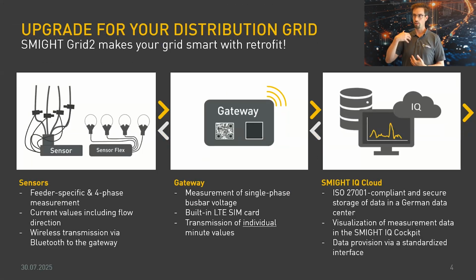At the moment, our product offering is very much oriented around feeder level monitoring. So we're talking about low voltage feeders within secondary substations and/or distribution cabinets. We do that with our sensors, which we put onto the feeder cables, one for each of the 3 power phases, but also for the neutral line. So we're taking those 4 phase measurements, measuring the current flow direction and magnitude, but also the phase angle.